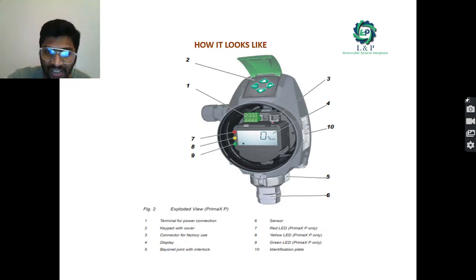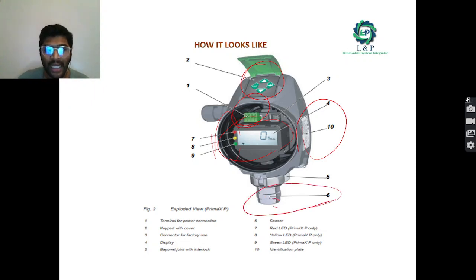As you can see, we have a display to show the values, and a keypad for operations. We have LED indications for showing the different statuses and error values. We have terminal provisions for connecting the power wirings and also for taking the relay output wirings. We have the identification nameplate, and most importantly, as you can see here, this is the sensor part of it. We have a bayonet joint with interlocks, so that we can interlock it if you are connecting inside pipes or ducts. Using the glands you can make a joint interlock of the concerned sensors, so that it will be fixed properly in the concerned locations.